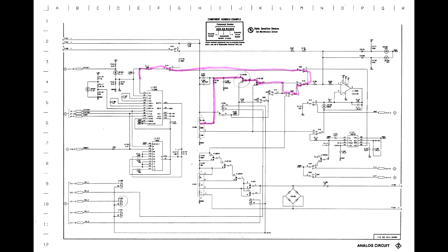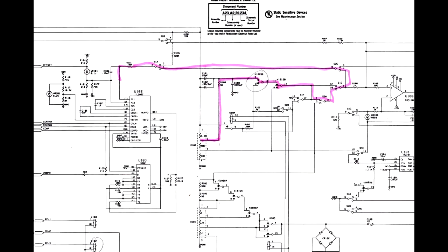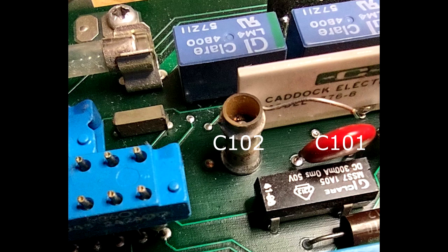Running out of things to check, I looked again at the input circuit. C101 and C102 are very small capacitors that are used to compensate the input divider for high frequency response in AC modes. C102 is variable to allow for different stray capacitances in the rest of the circuit. Both of the capacitors need to withstand most of the 1000 volt maximum input. C101 is rated at 4 kilovolts. C102 is rated at 750 volts according to the parts list. So it appears to be underrated.